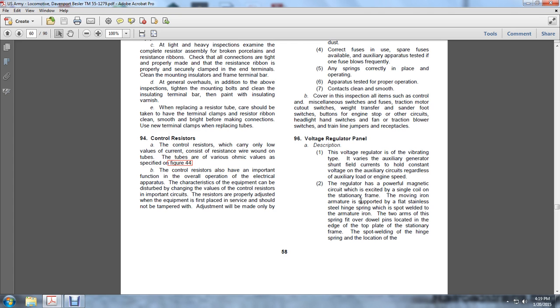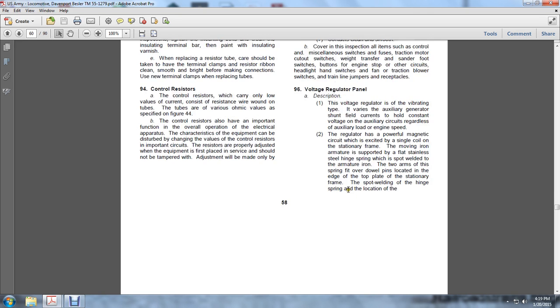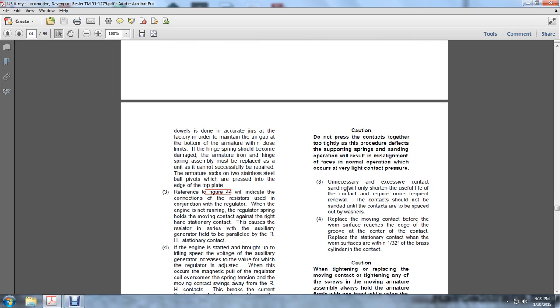The spot welding of the hinge spring and the location of the dowels is done accurately in jigs at the factory in order to maintain the air gap at the bottom of the armature within close limits. If this hinge spring should become damaged, the armature iron and hinge spring assembly must be replaced as a unit, as it cannot successfully be repaired.